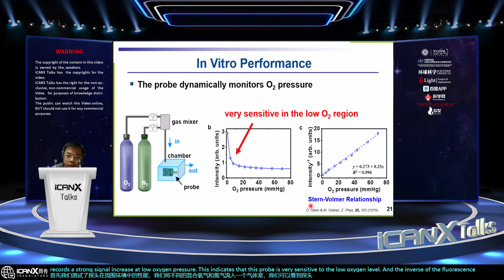And first, we tested the probe performance in an ambient environment. We flowed different mixed oxygen and nitrogen into a gas chamber, and we can see the probe records a strong signal increase at low oxygen pressure. This indicates that this probe is very sensitive to low oxygen levels. And the inverse of the fluorescent intensity is proportional to the oxygen pressure. This follows the standard classical Stern-Volmer relationship.